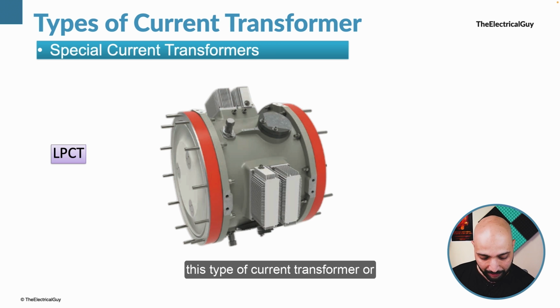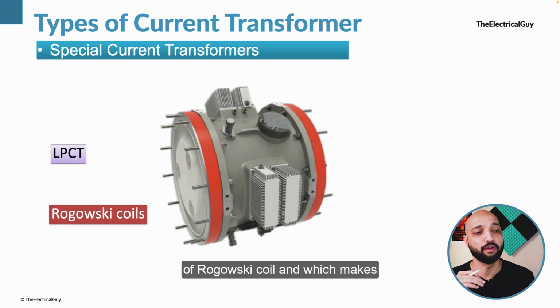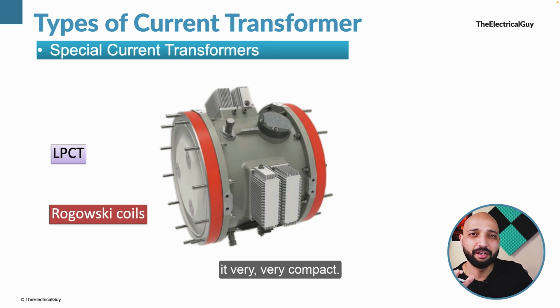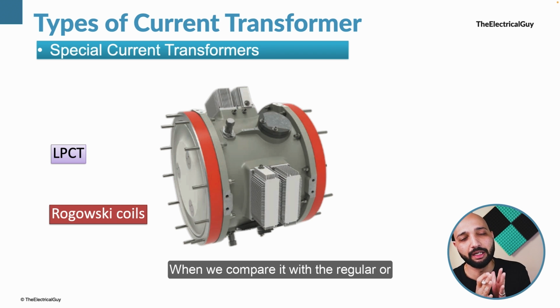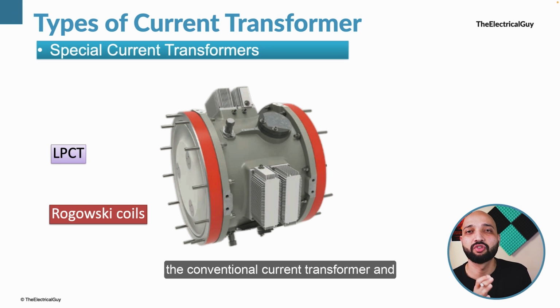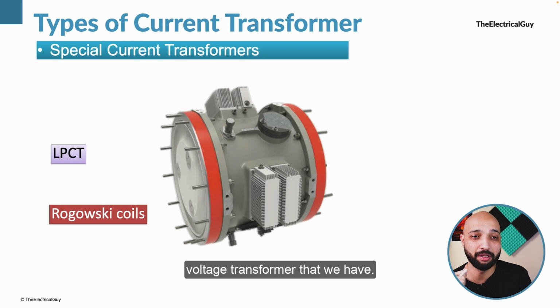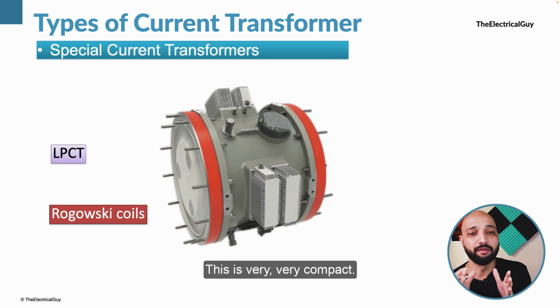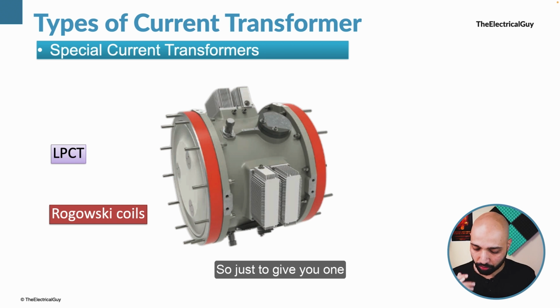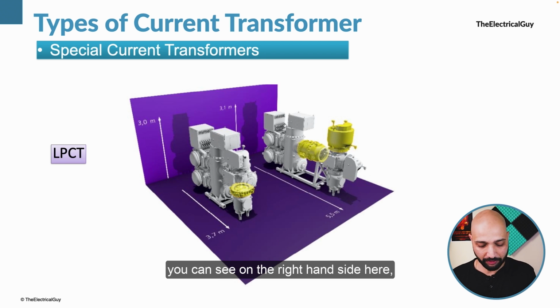This type of current transformer or voltage transformer uses the principle of Rogowski's coil, which makes it very, very compact when we compare it with the regular or conventional current transformer and voltage transformer that we have. It is very, very compact.